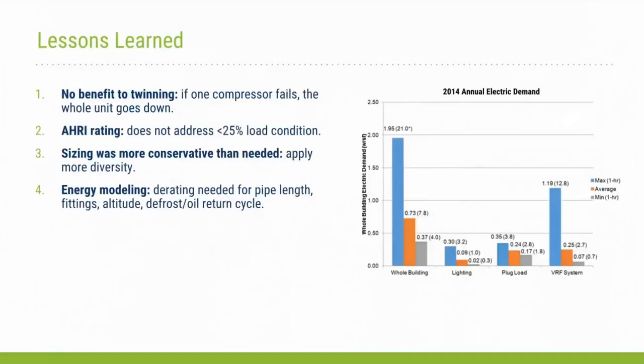One thing we found is that there is really no benefit to twinning in this particular application for a water source application, unlike a system that might have 2 compressors. In this type of condition with this manufacturer, if one compressor fails, actually the entire unit goes down.